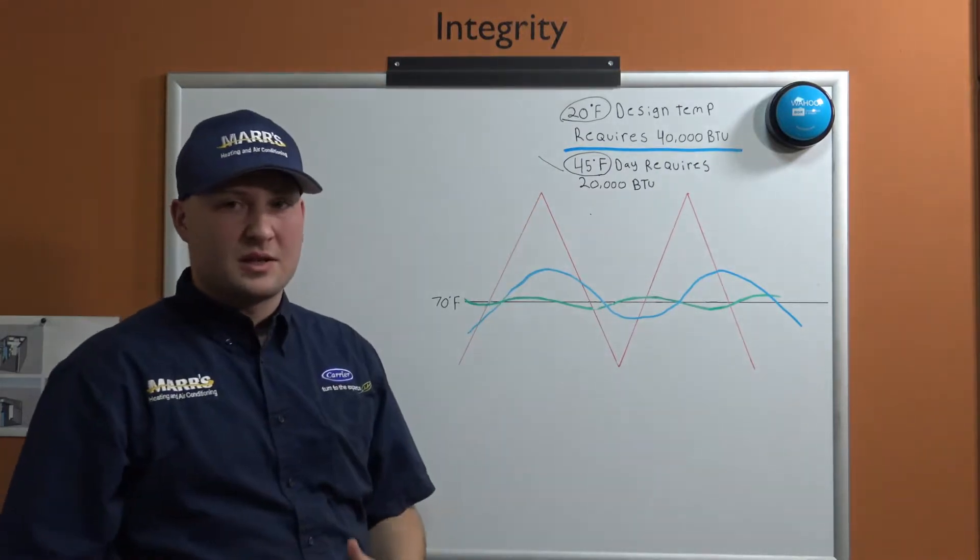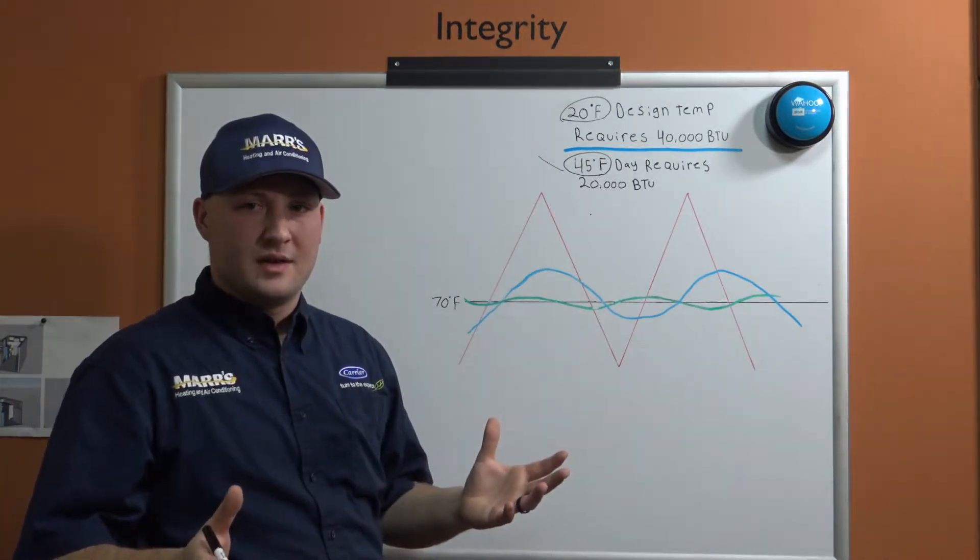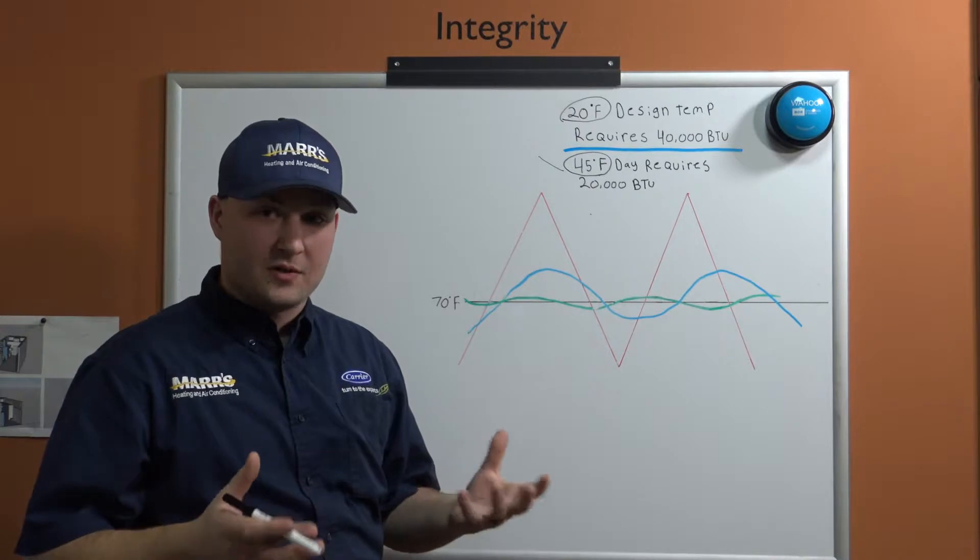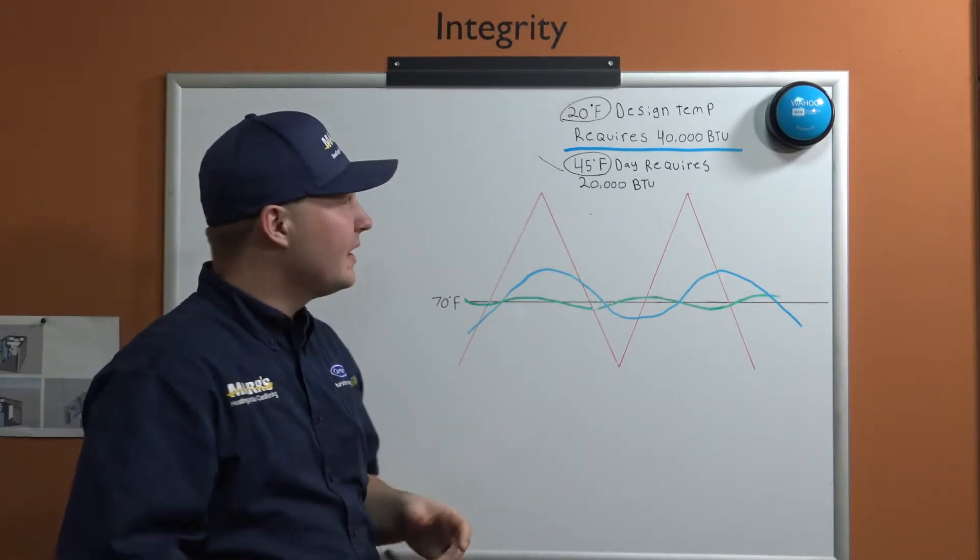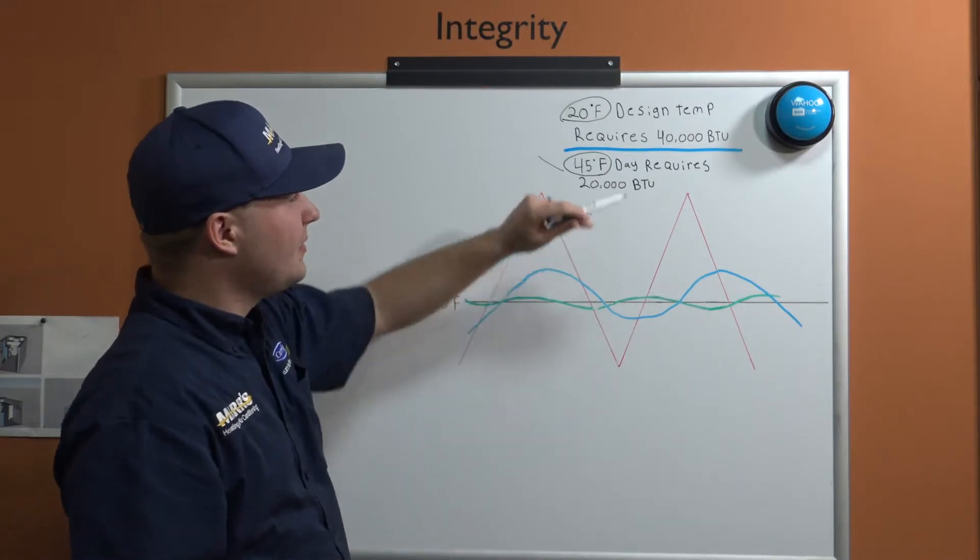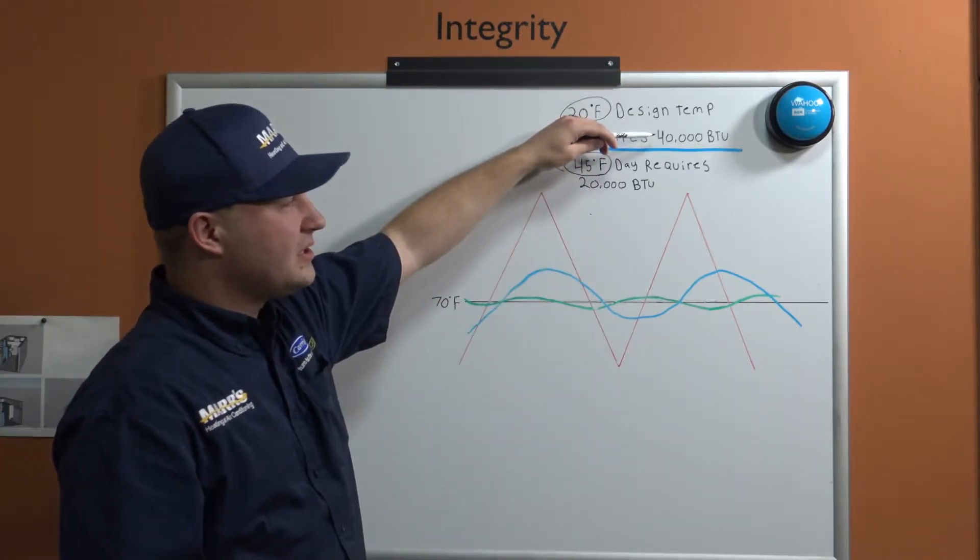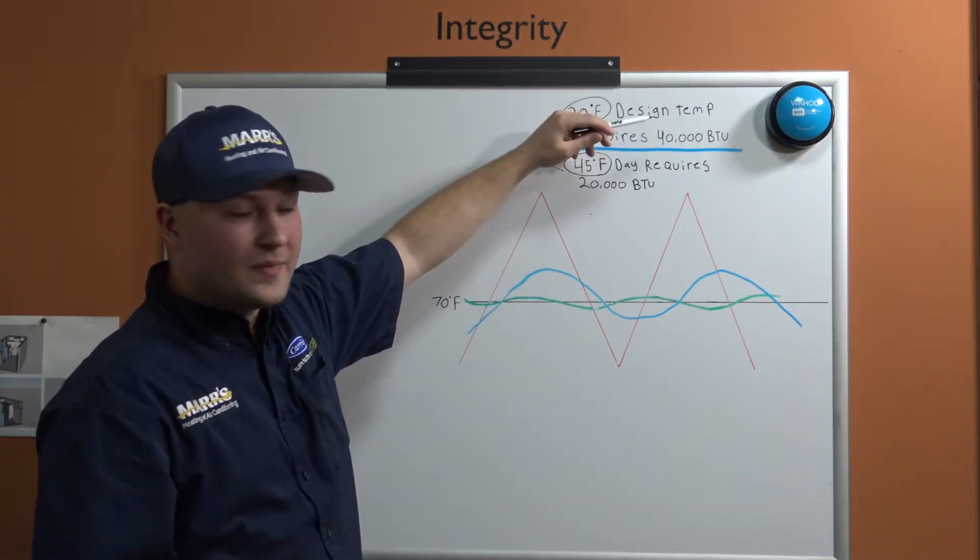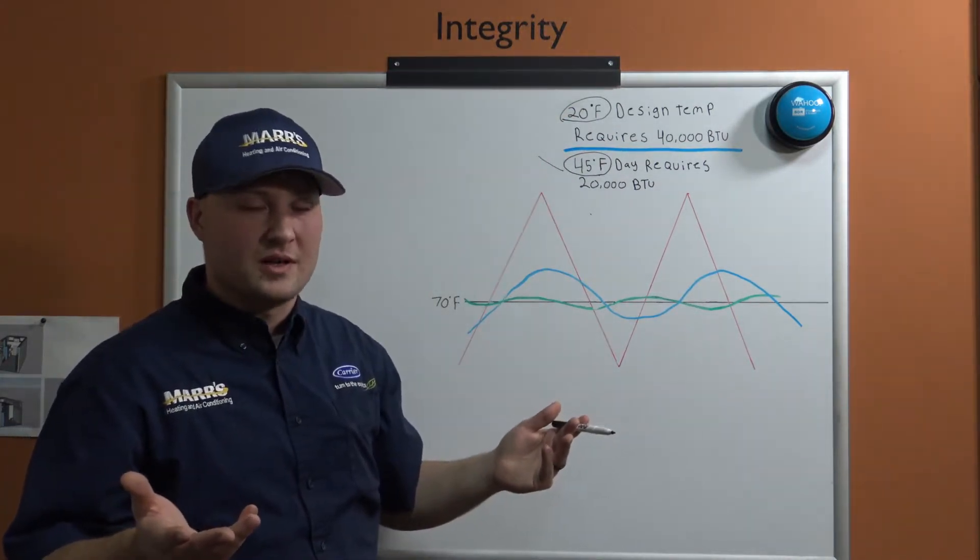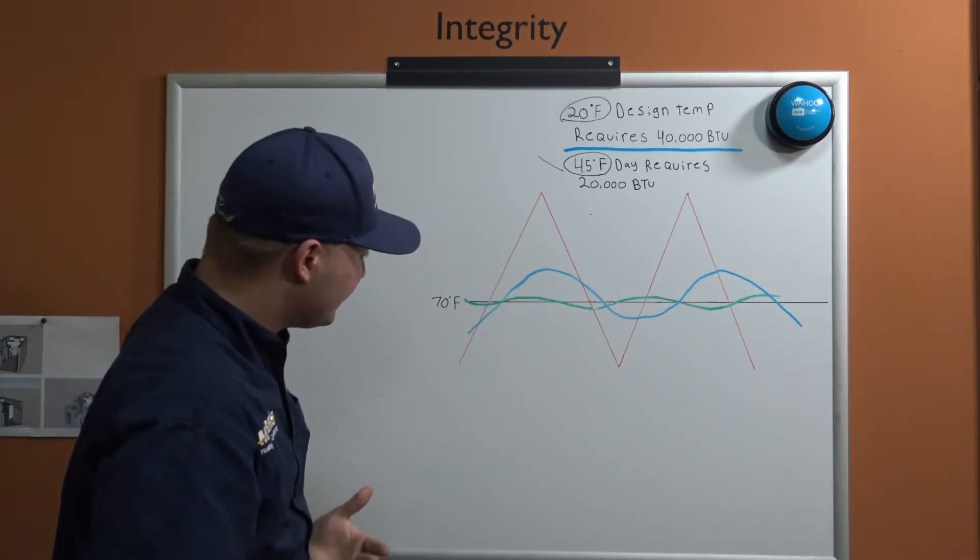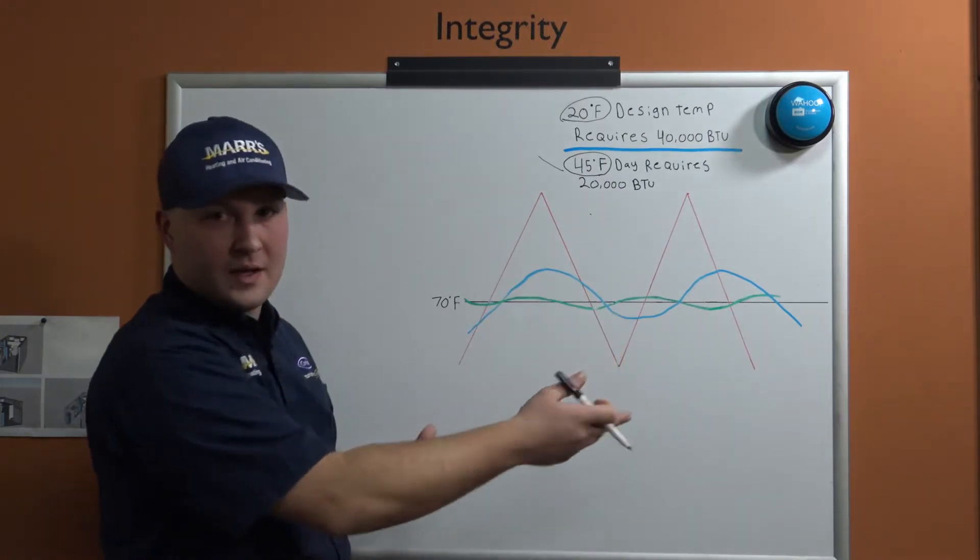So the majority of the time our equipment is actually way oversized, and that's the reality with single-speed equipment. We're either 100% on or 100% off. For this home maybe we have a 40,000 BTU capable system, but really we only need 20,000 for the majority of the time the system's running.